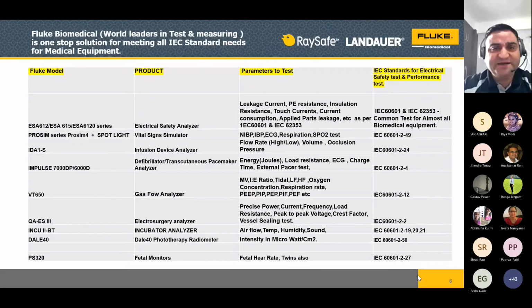Same way, defibrillators. You give an electric shock to make your heart rhythm normal when it is abnormal. So you have to check energy. Suppose I am giving 250 joules to the patient, whether 250 joules is actually being delivered or not. At that time, what is the ECG waveform? Charge time. Suppose we claim you have to deliver energy in 6 seconds. If it is delivering in 15 seconds, it is of no use for the patient. So these are all specifications which manufacturers have published in the catalogs, and they have to be met, checked with these kinds of simulators or analyzers.